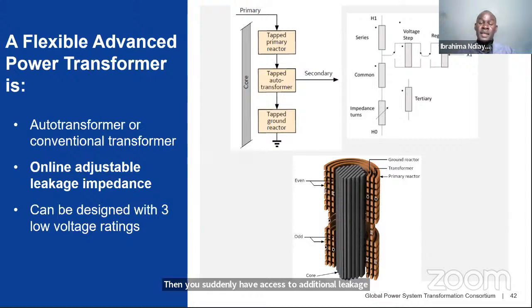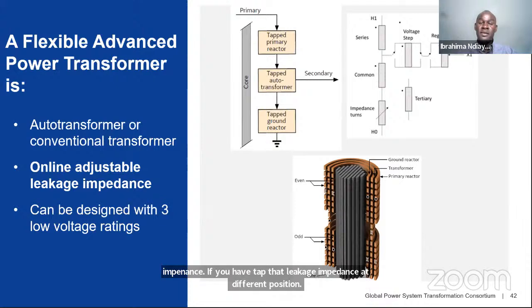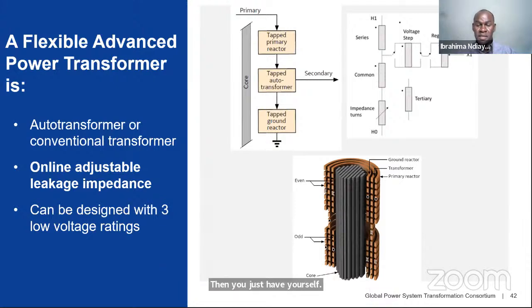If you tap that leakage impedance at different positions, then you have yourself a variable leakage impedance. If you complete that design with a tap changer, as we use today for voltage, then suddenly you have a transformer with variable leakage impedance. That's really how we developed that technology.